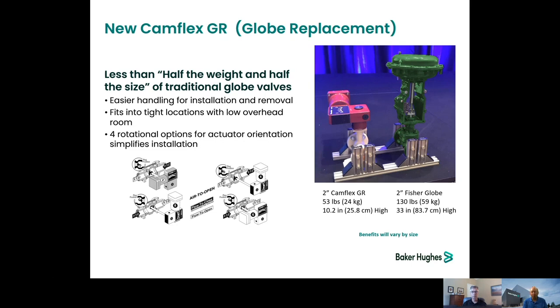And here I should also point out that, obviously in the picture, those two valves are the same line size, but you can see the Camflex is much smaller. A lot of that is due to the smaller actuation that's required, or rather, conversely, the larger actuation that's required on the conventional globe. That smaller actuator package allows the Camflex to fit in virtually all applications where a globe valve would have been in service originally.